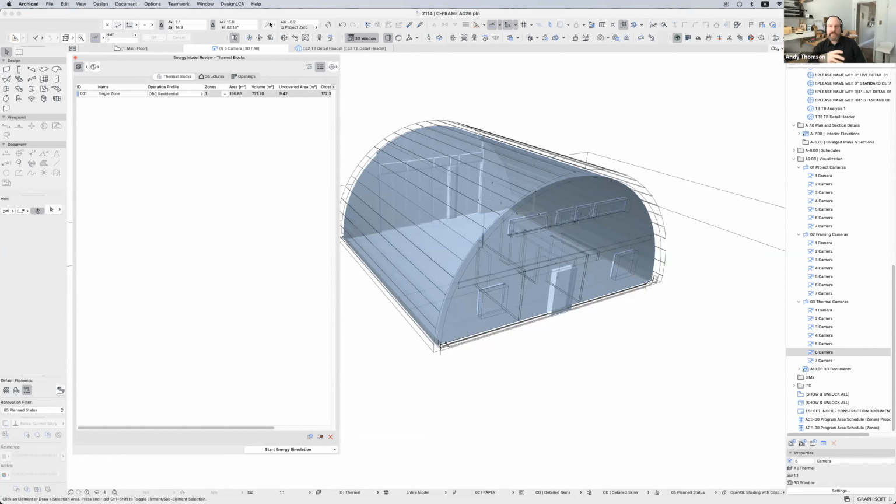And we had a really interesting test case, that wedding building that I was talking about in Innisfil, where the engineer's model was coming up with 22 tons of cooling required. And our model was showing we needed about 7 tons of cooling. So it's not that we are engineers and we're trying to do engineering, but we just have a question for the mechanical engineer. How are you getting 22 and we're getting 7?